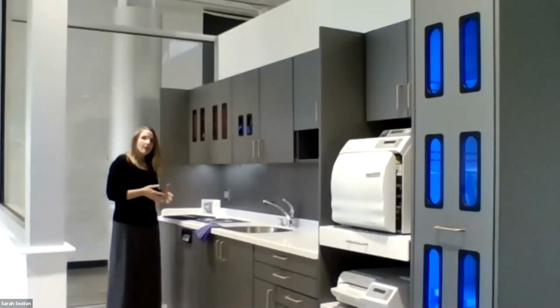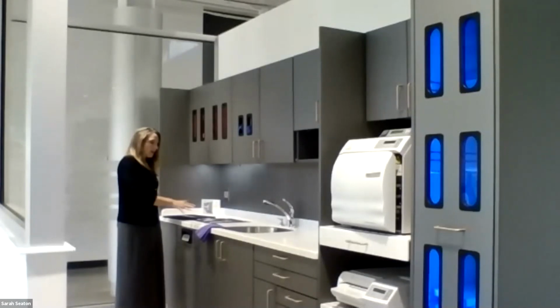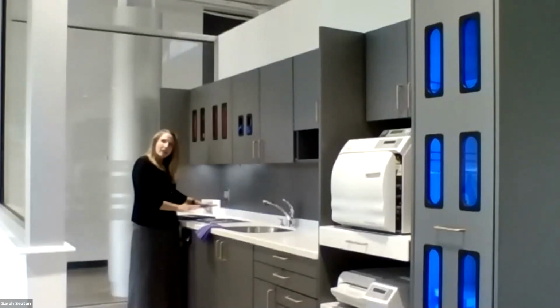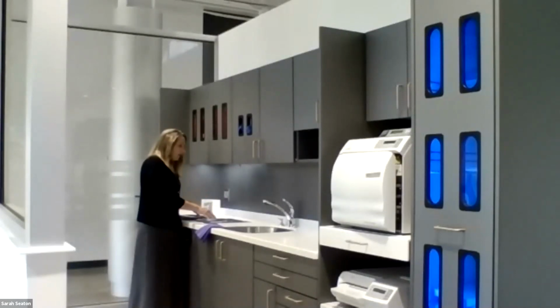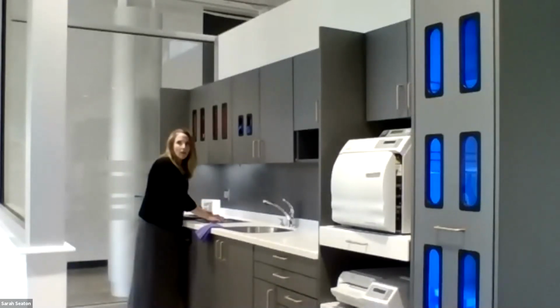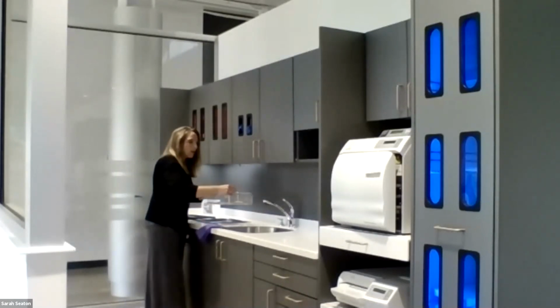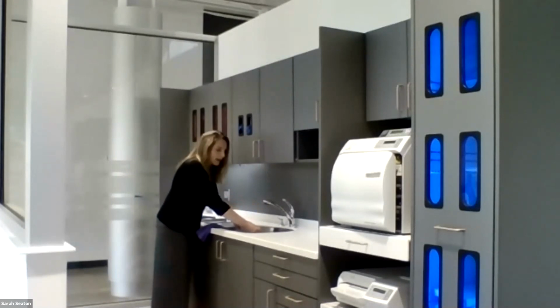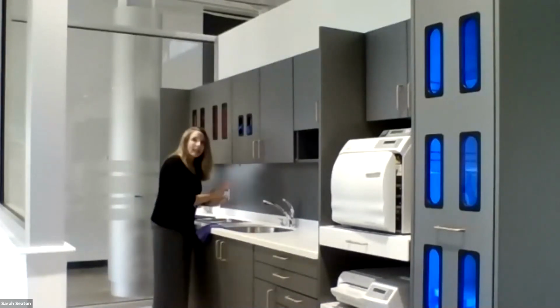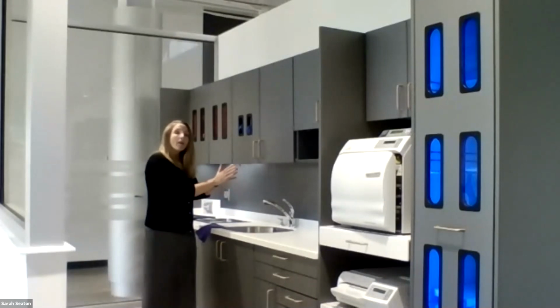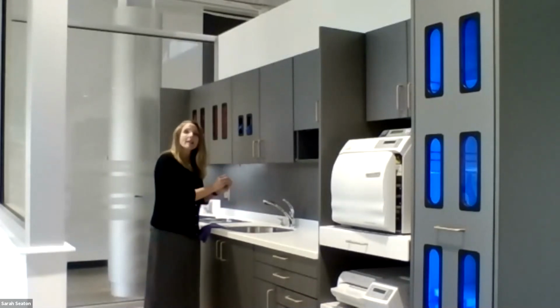So some of the pitfalls that we've seen happen in this first section we call the cleaning area is that it's not big enough. There's not enough counter space. Another area that has to happen is when after they clean the instruments using an automatic cleaner, which is what we recommend, they want to make sure there's a sink big enough to accommodate the basket. Because after they clean the instruments, they come down here and they rinse the instruments and they inspect them to ensure that the instrument actually got cleaned and that there's not any bioburden left on those instruments.